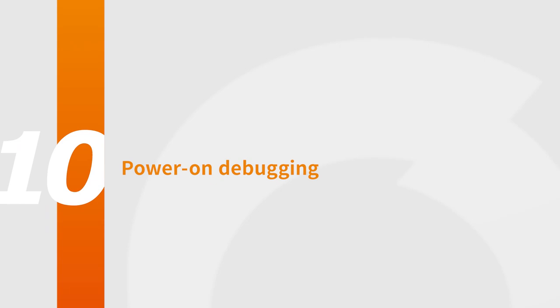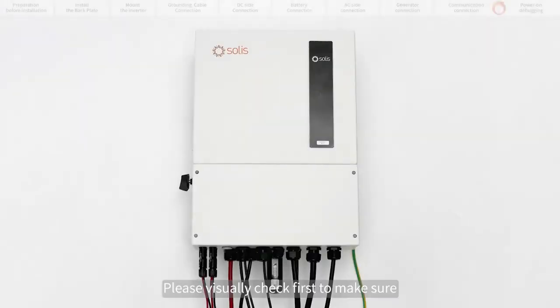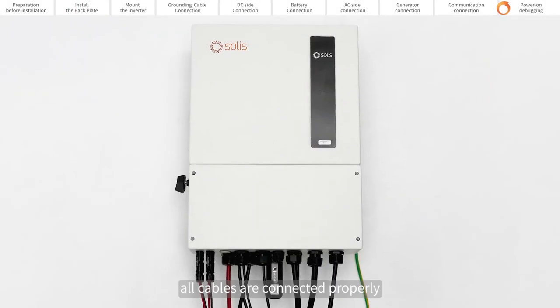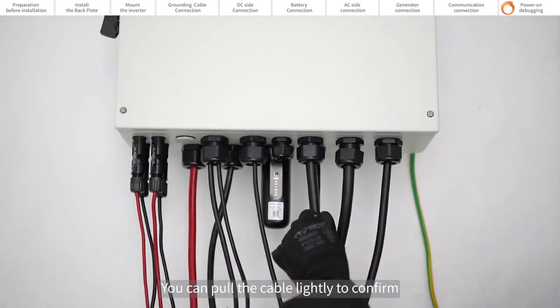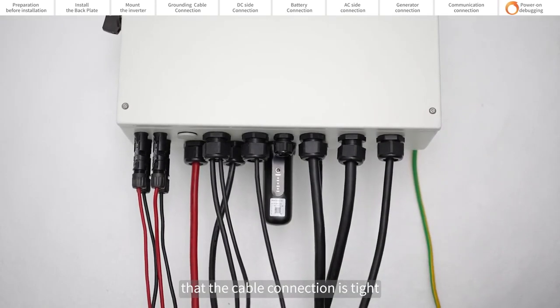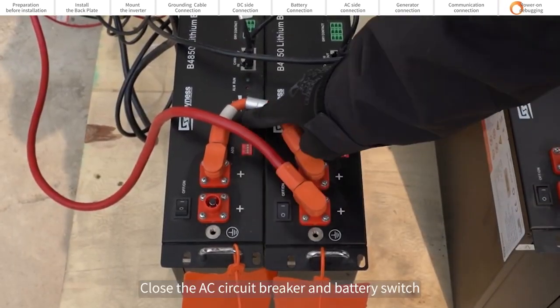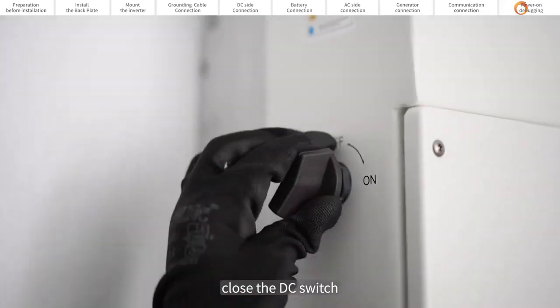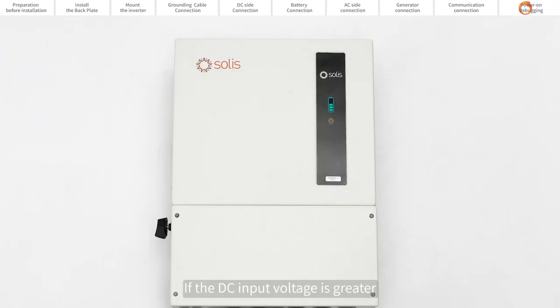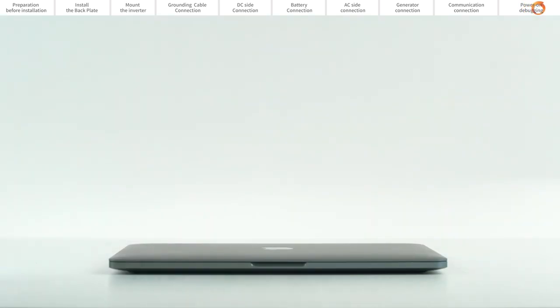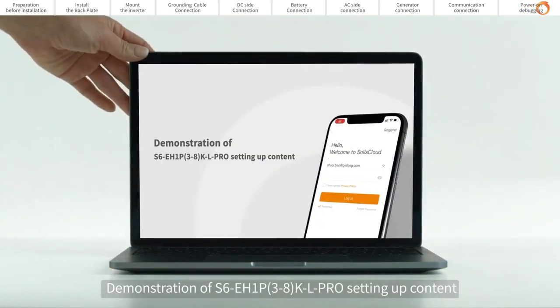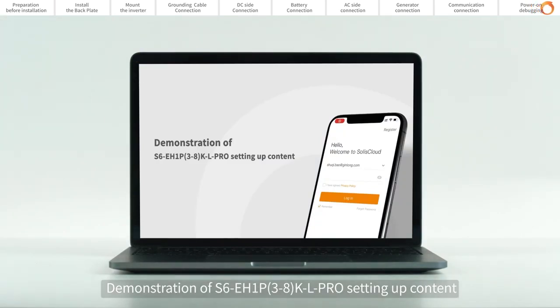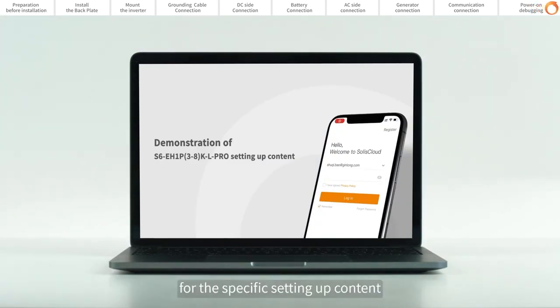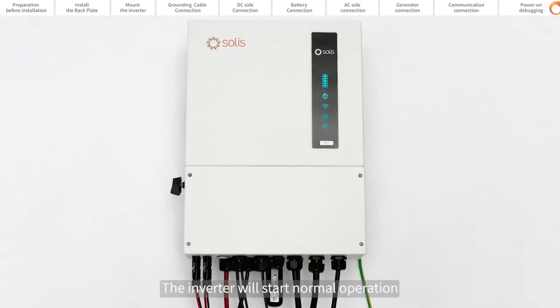Power on debugging. Please visually check first to make sure all cables are connected properly. You can pull the cable lightly to confirm that the cable connection is tight. Close the AC circuit breaker and battery switch. Close the DC switch. If the DC input voltage is greater than the startup voltage of the inverter, it will start up. Connect the app for debugging. Please refer to the demonstration of S6-EH1P 3 to 8K-L Pro setting content for the specific settings. The inverter will start normal operation.